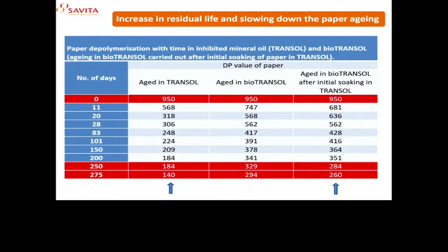and all cellulose materials. So what we did in Savita, we did one experiment. We took insulation paper and dipped it first into the mineral oil. Then after that, we introduced it into the natural ester fluid, and at 160-degree temperature, over a period of 0 to 275 days, we observed the depolymerization, because the DP value is the indicator of the health of the insulation paper. So the result is in front of you.